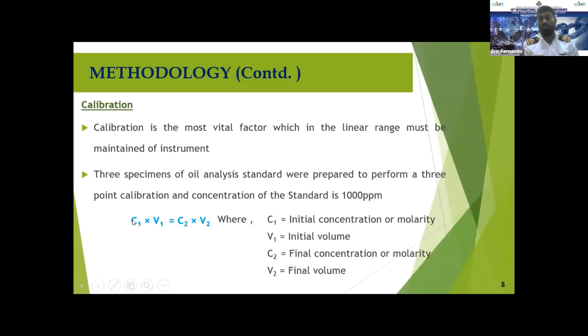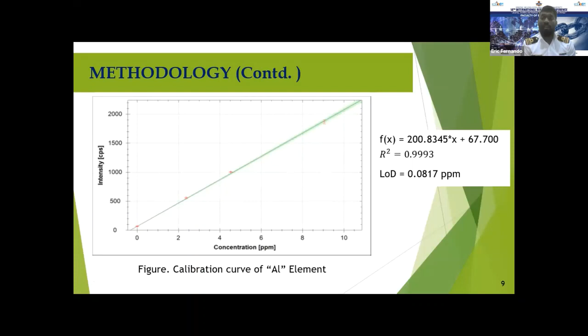During the calibration, this is an example of the calibration curve of the aluminium element. You can see this 3-point calibration. We have to maintain the linearity closer to 1. If this R square value is closer to 1, it means that your calibration is perfect. On the other hand, we have to always think about this LOD value, which is called the limit of detection. If the limit of detection value is greater than the results we are getting for the aluminum element concentration, then those results should not be considered, and we have to introduce another sample in order to have better results.